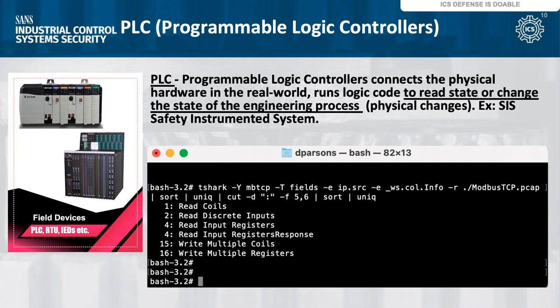So this programmable logic controller uses a lot of industrial processes inside and underneath it. On the screen here we can see a wire capture of industrial control system commands going across the wire. In this case, we see Modbus TCP, a specific industrial control system protocol being utilized, showing read state and change state commands in the actual code on the wire—this is read coils and write multiple coils and registers.